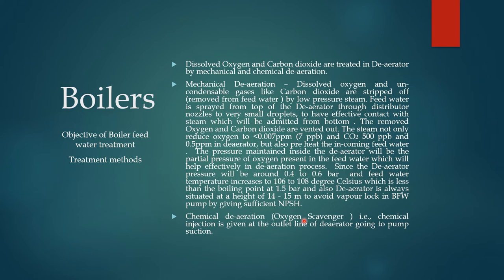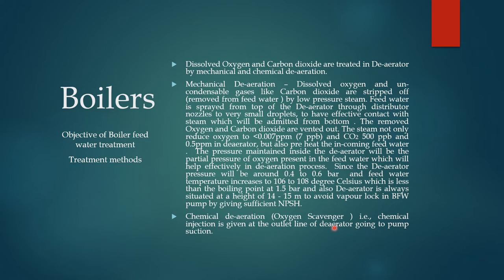For chemical deaeration, an oxygen scavenger chemical is injected at the outlet line of the deaerator, which goes to the pump suction after mechanical deaeration. The deaerator outlet line coming through headers goes to the pump suction, and immediately after the deaerator, the oxygen scavenger is injected at the outlet end of the deaerator.